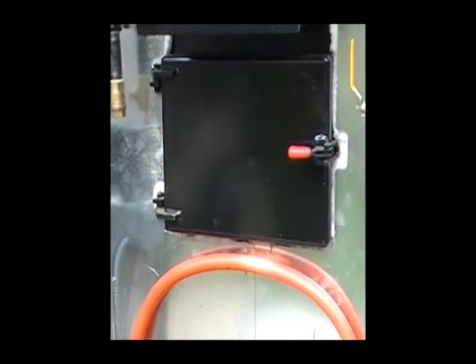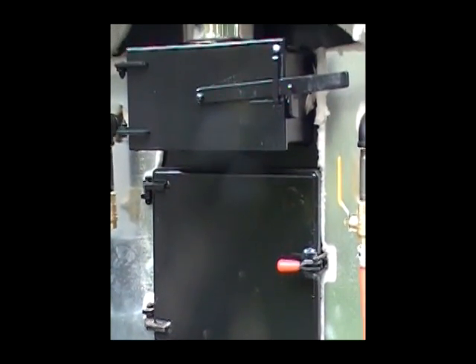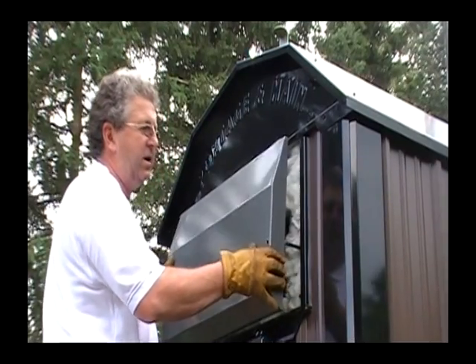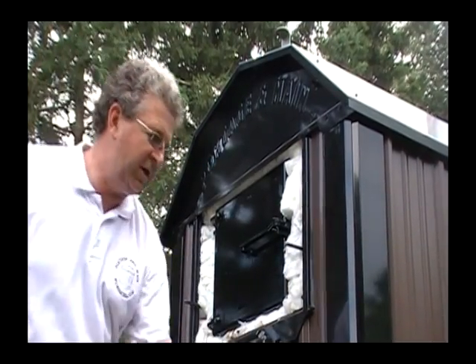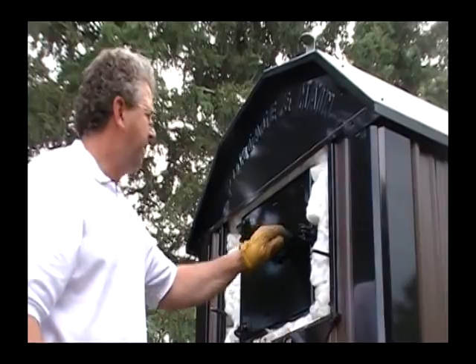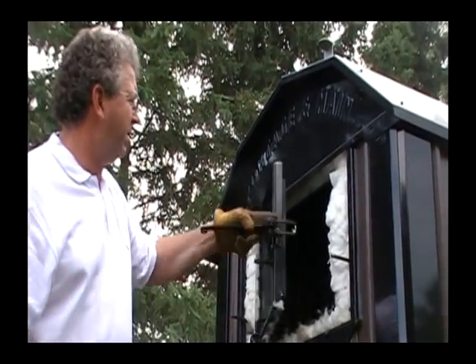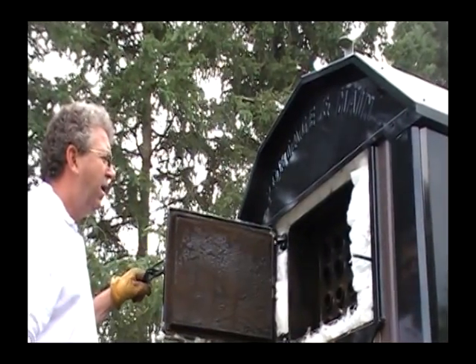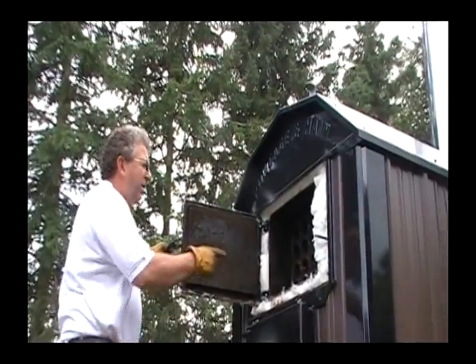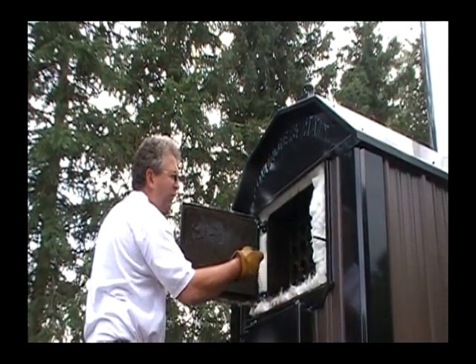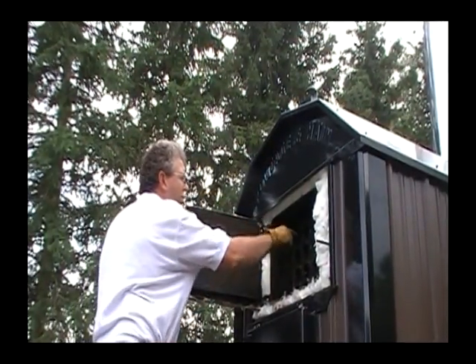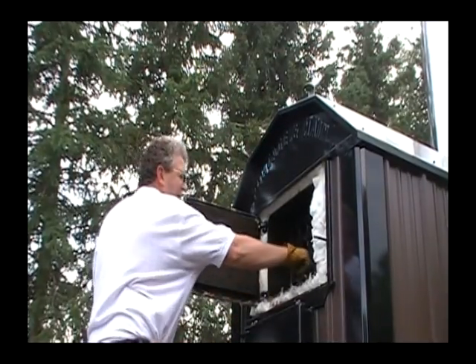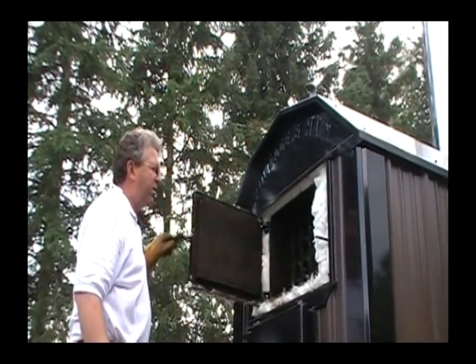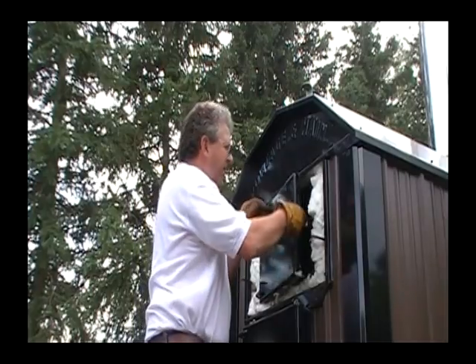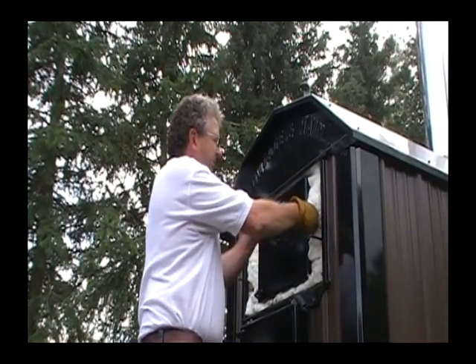Let's go around to the front and have a look at the front of the heat exchanger. Behind here is the access to the front part of the heat exchanger. Easy to access, again on hinges, and all you're going to see is that's where the heat has to come up from the bottom through this set of tubes, turns around and goes to the back. Still very clean, but a little bit of dust in there, but easy to access, easy to get at, easy to service.